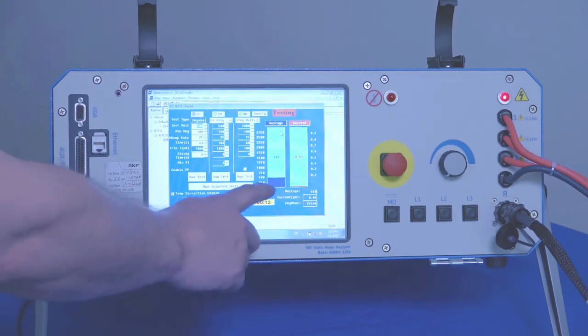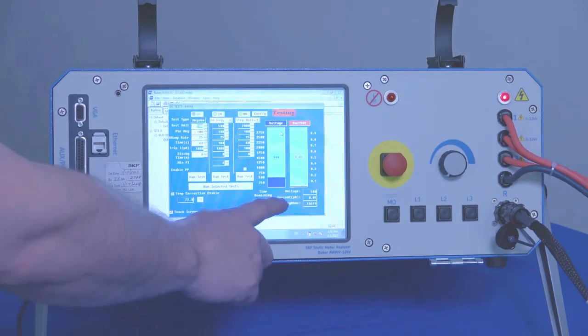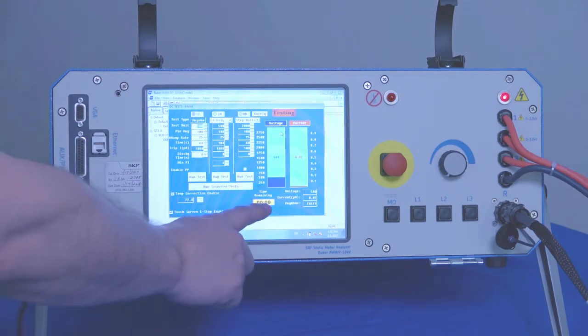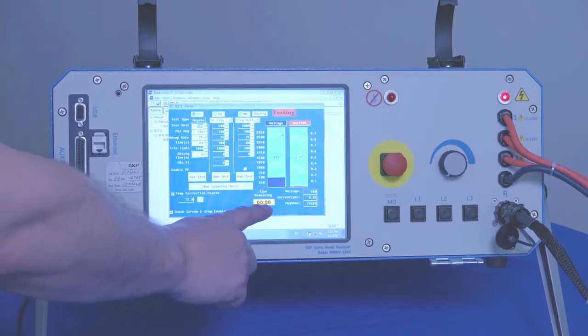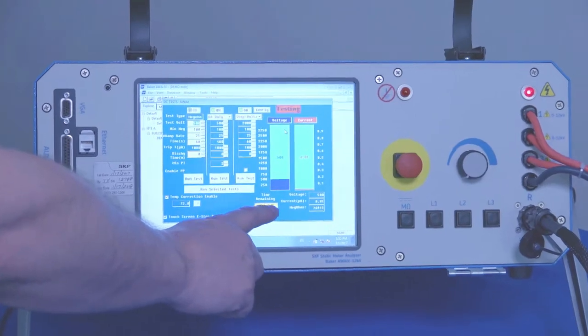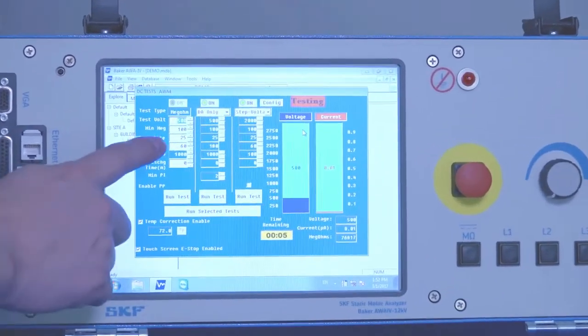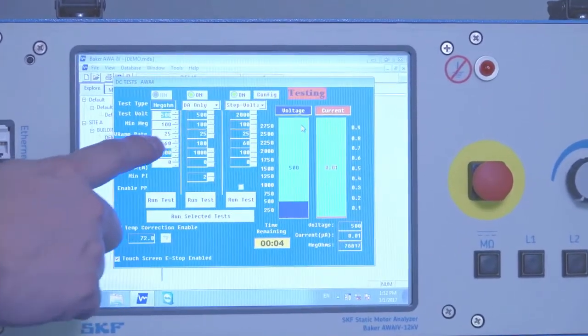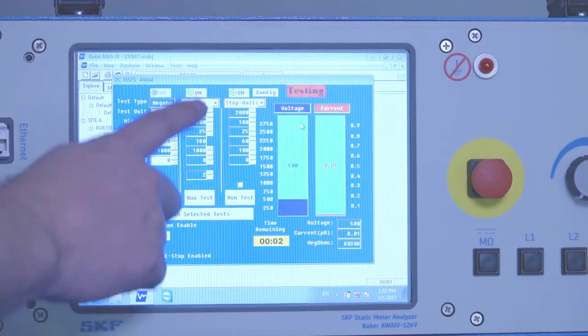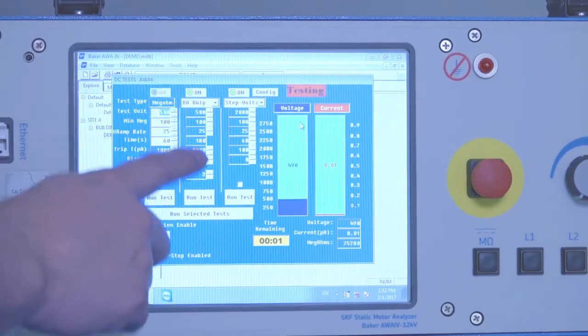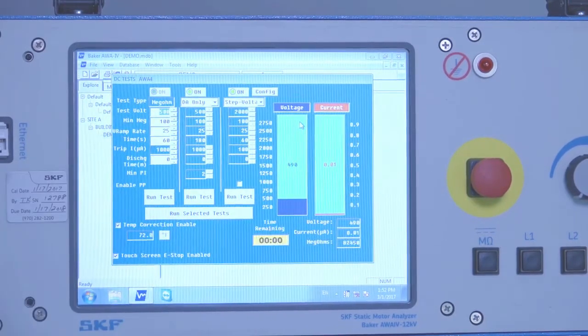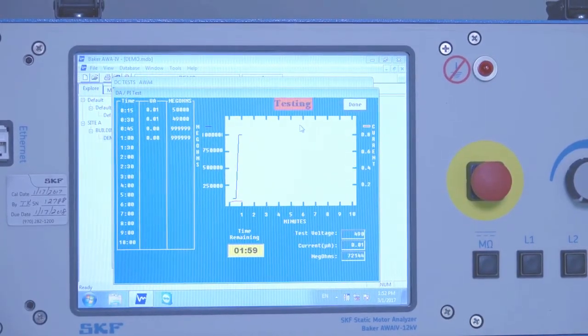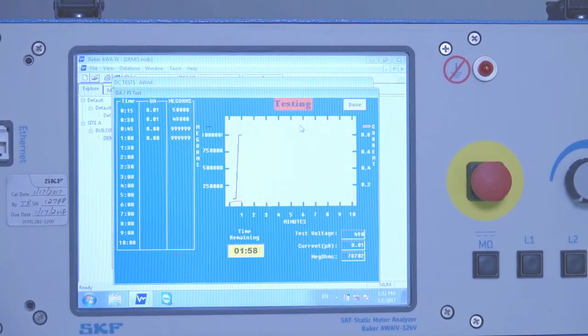So the timer started when we achieved test voltage. Once the one minute timer times out based on the time set here, we'll proceed to the next test, which is the DA in this case, dielectric absorption test.